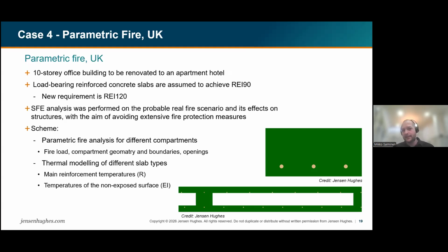So the problem here was that the structural engineer had confirmed that the slabs achieve 90 minutes fire resistance, and now the requirement would be 2 hours because of the renovation and change of occupancy. So what we wanted to do was to investigate if this 90 minutes rated... So this 90 minutes always refers to the standard fire. So if this 90-minute rated structure would survive a full realistic fire scenario, that's what we wanted to investigate. So we did again the fire simulations, or the parametric fire analysis, and thermal modeling of the slab structures.